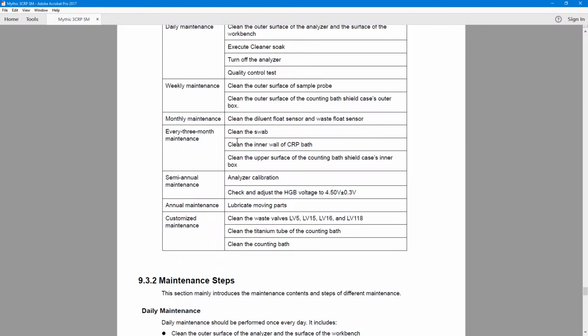Every 3 months, clean the swab, clean the inner wall of the CRP bath, and clean the upper surface of the counting bath shield case inner box. So, the swab and rinsing head. Especially underneath, you will see some dry reagents and maybe some blood residues, so this needs to be cleaned. Clean the inner walls of the CRP tube: you will take some kind of cotton swab and just gently clean the inside with deionized water.